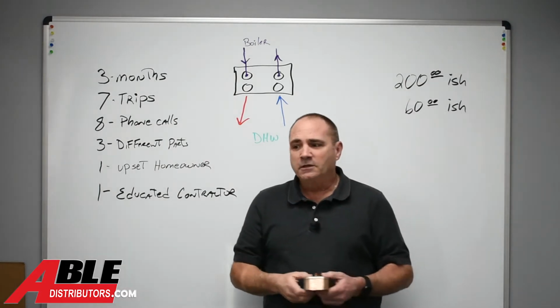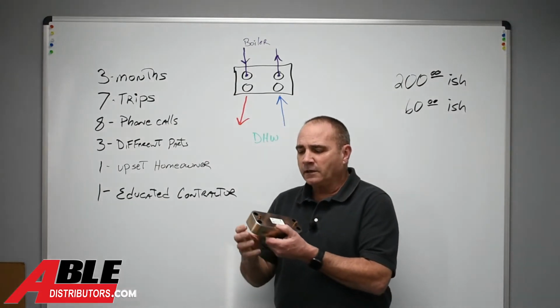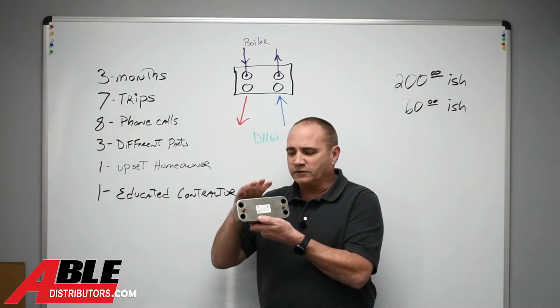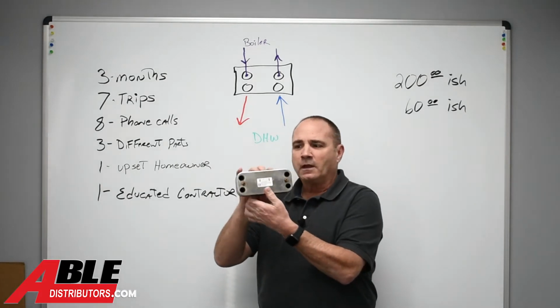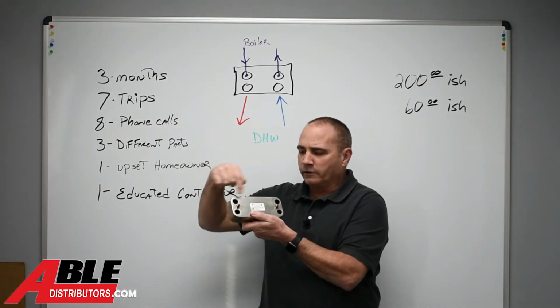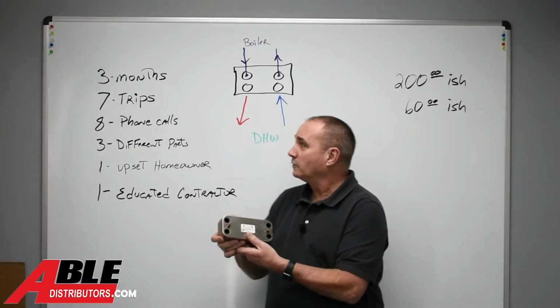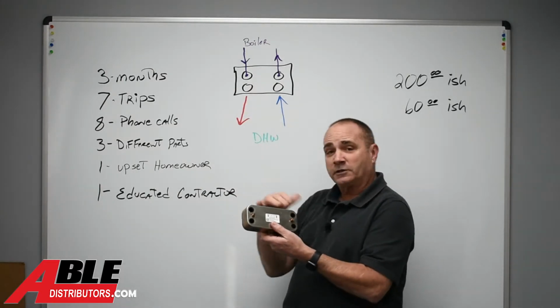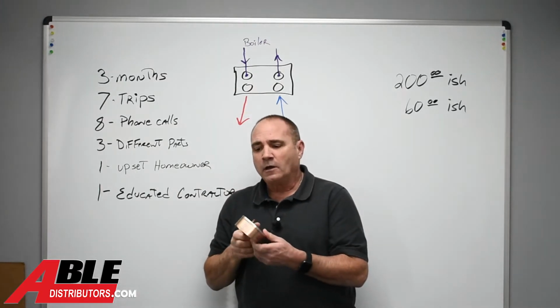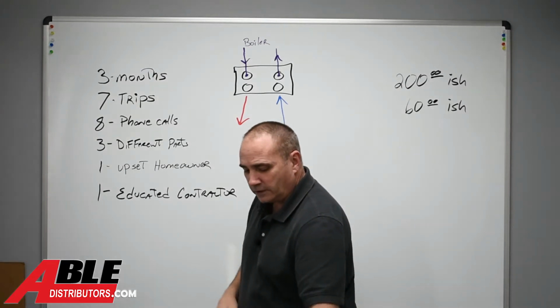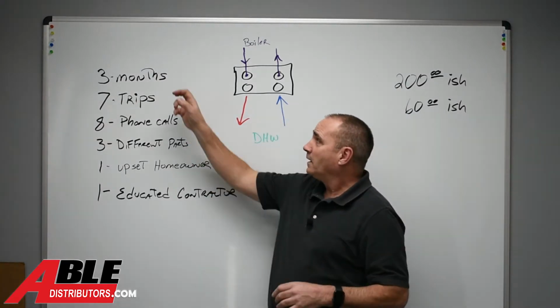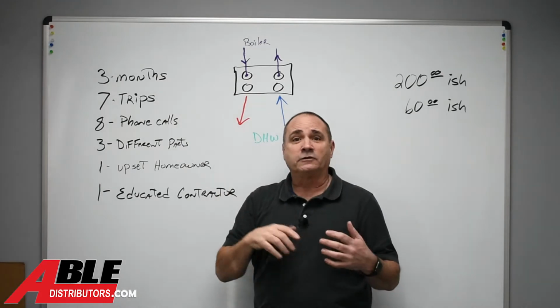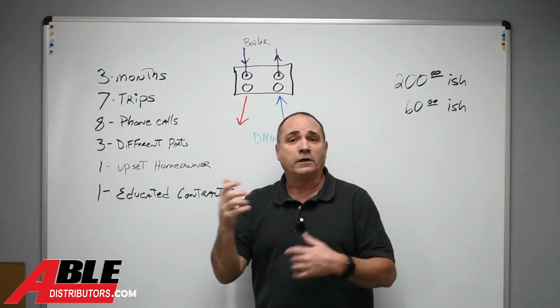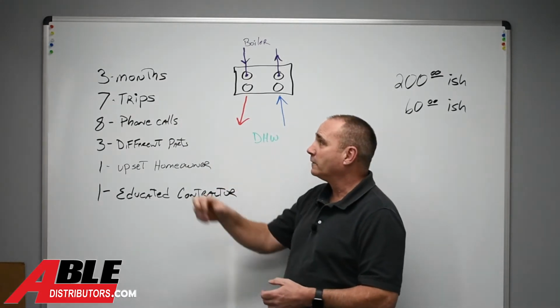The reason for all the problems was this flat plate heat exchanger. The boiler water goes through the top, the domestic water goes through the bottom, transmits the heat, heats your water. Well, we had issues, and the numbers on this job: 3 months after the install, it started failing, overheating, having problems with the domestic hot water.